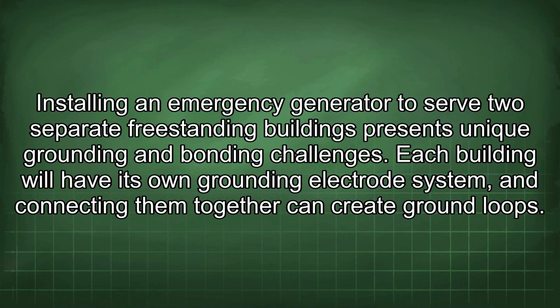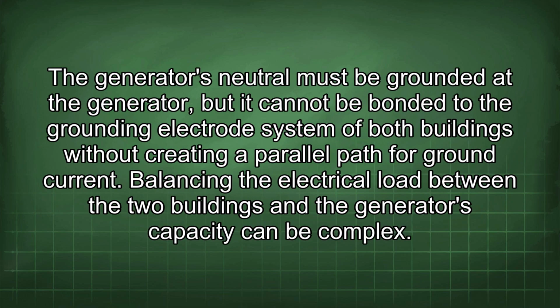Installing an emergency generator to serve two separate freestanding buildings presents unique grounding and bonding challenges. Each building will have its own grounding electrode system, and connecting them together can create ground loops. The generator's neutral must be grounded at the generator, but it cannot be bonded to the grounding electrode system of both buildings without creating a parallel path for ground current.